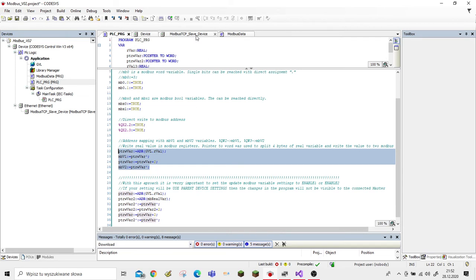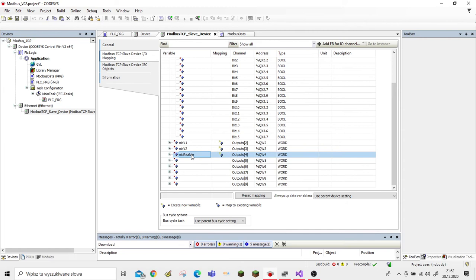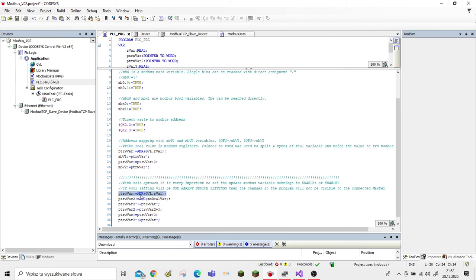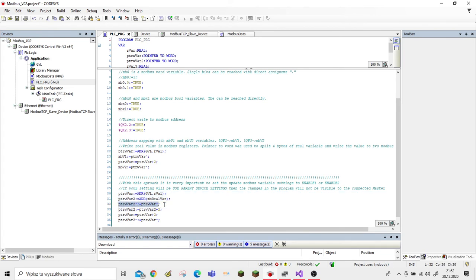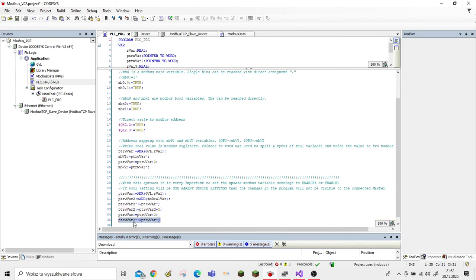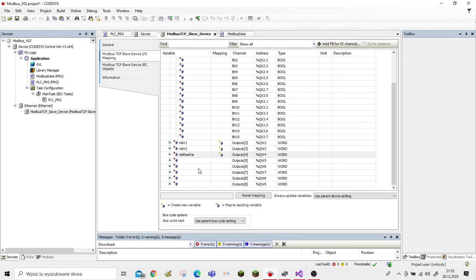Another way to send a REAL value is to assign only one register, but it is a little bit tricky and requires proper settings in our Modbus configuration. We declare the address, assign the address of our REAL value to the pointer, and also a pointer to our Modbus variable. We assign the first two bytes to our Modbus register, then jump two bytes forward to get the second two bytes from the REAL variable and assign them to the proper register.